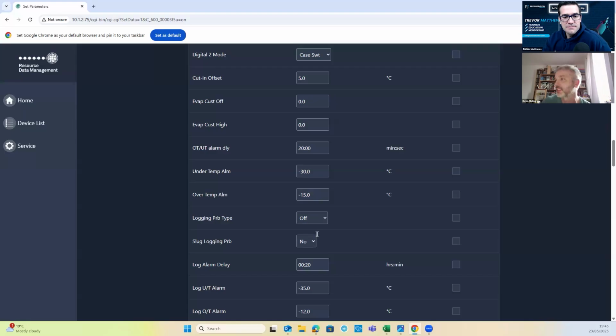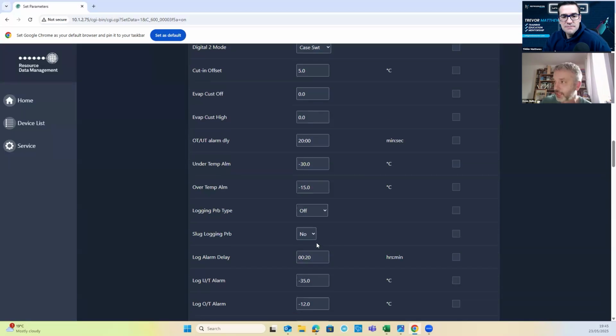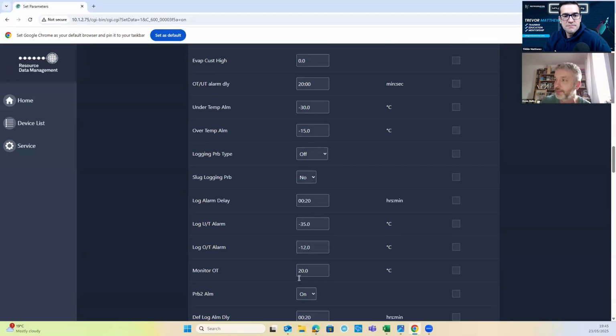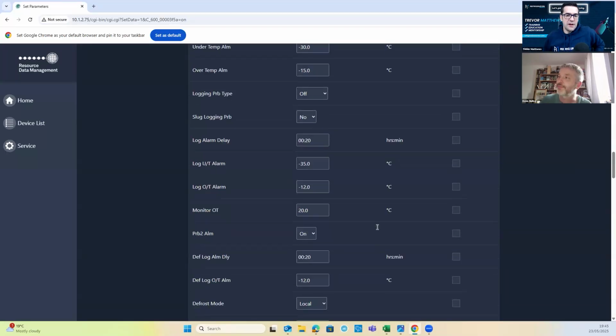So that goes into probe 6, usually, on an RDM controller, and it's got its own temperature ranges. Okay. Yeah. There's tons of them. Oh, hundreds. I'm not going to go through all of them. Probe 2 is useful if you've got a controller, let's say you're putting an RDM controller in something that only had an evaporator probe and an air probe previously, and you just want to retrofit it.